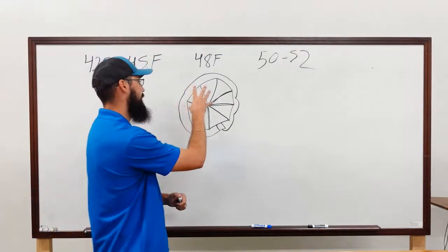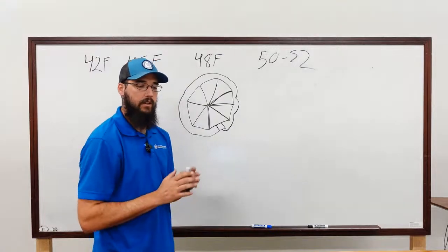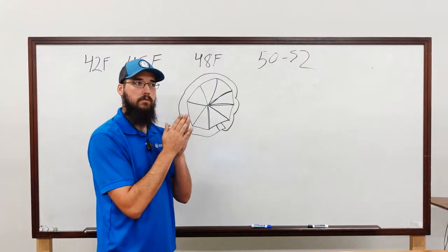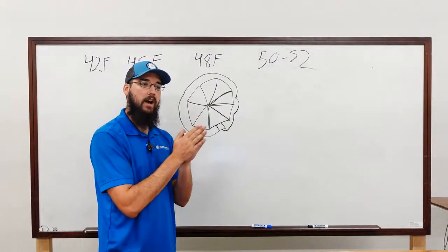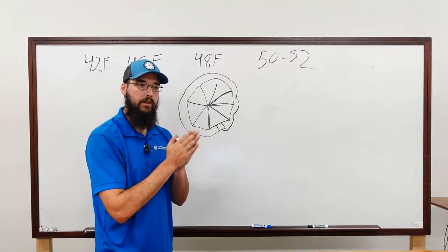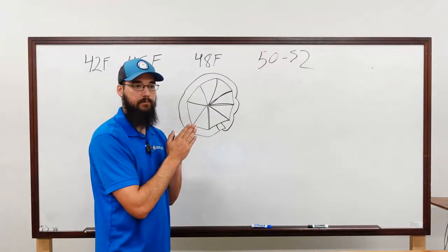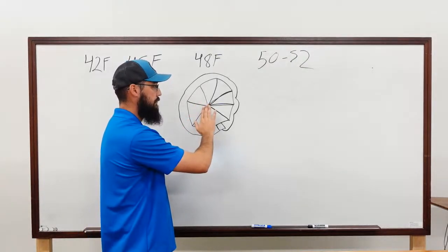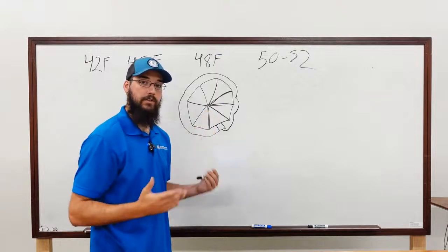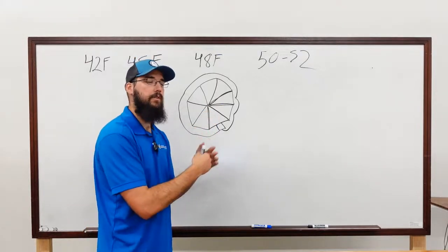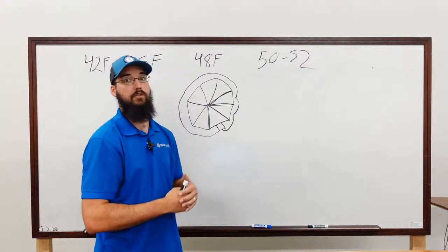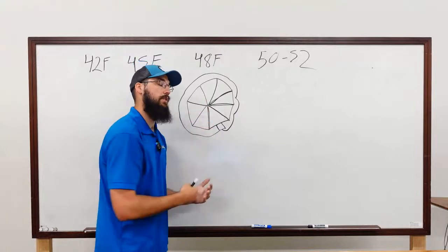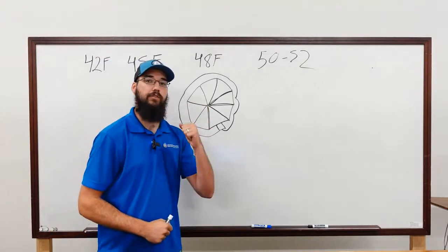All right, the second thing that the IGV gives us is loading control, by literally changing how much refrigerant is allowed to make it to the impeller. So when this is closed, we're essentially not allowing refrigerant through. Now, obviously, it doesn't make a perfect seal, so it's not that there's no refrigerant, but we're talking it might as well be, to the extent that these are able to unload. This is extremely critical for startup.